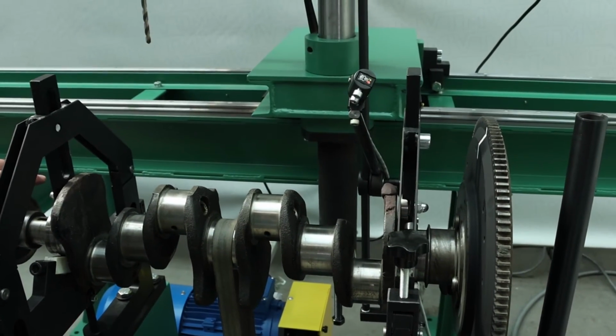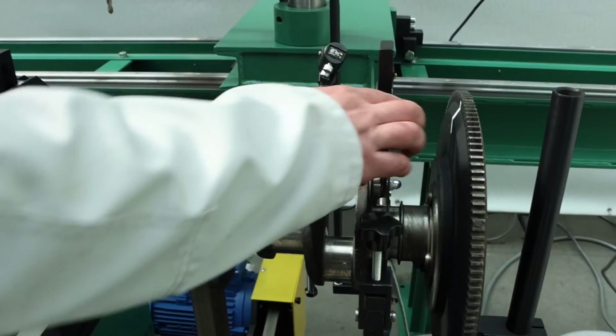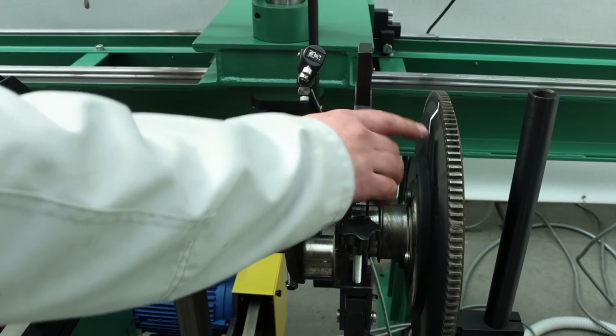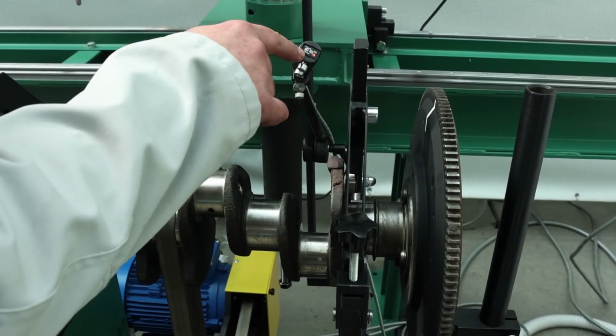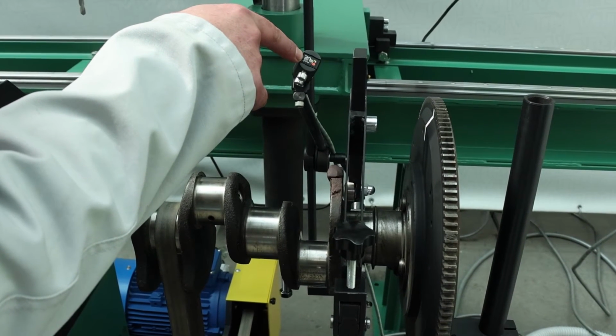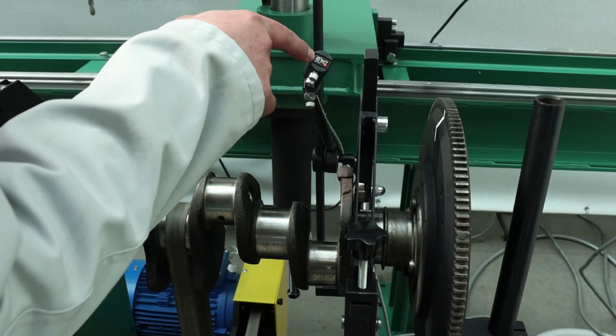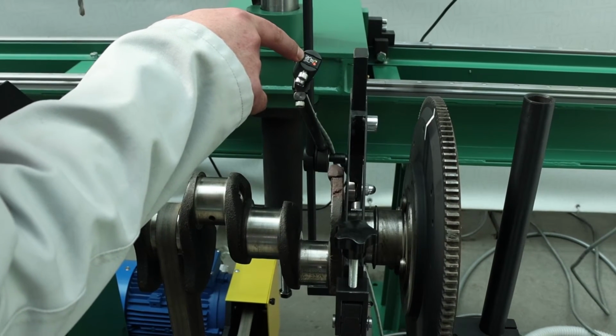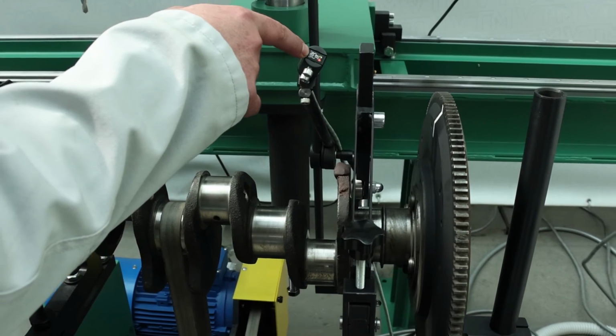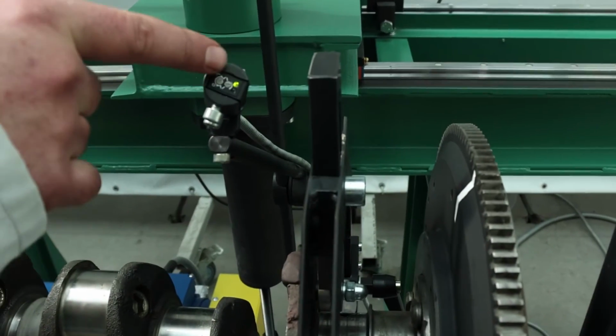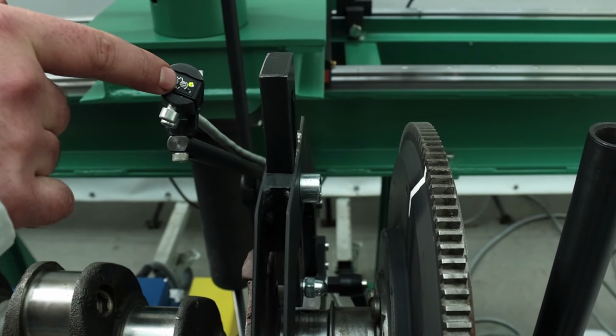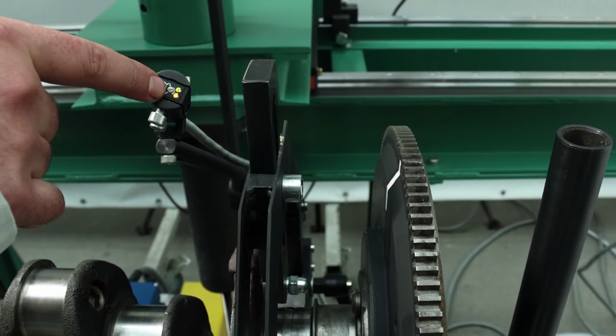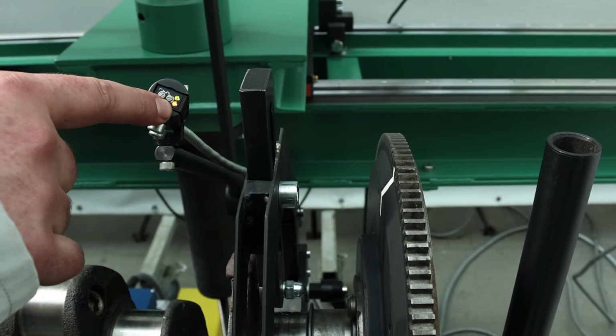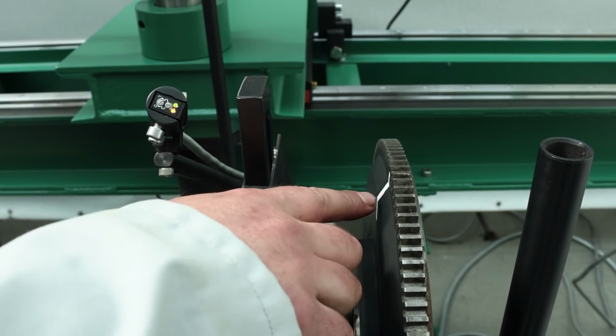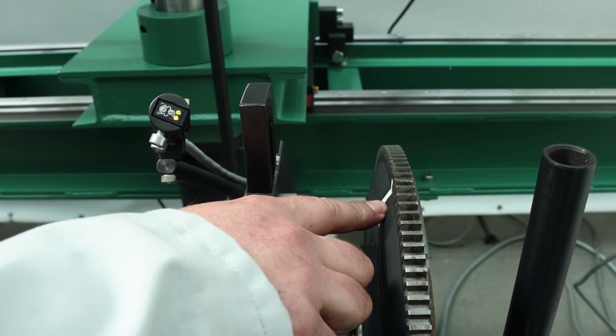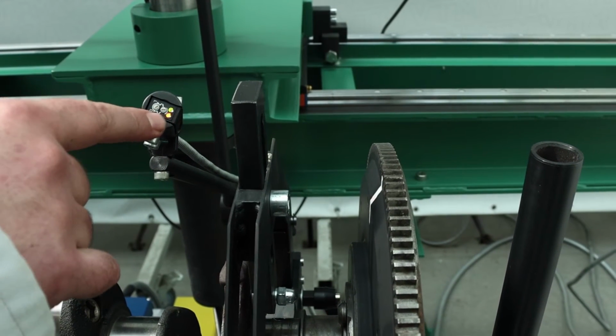To optimize the laser setting, a contrast mark should be made, preferably on a dark background. And set the switch, potentiometer, upper to position L. So that would mean that the light mark is now selected. And then turn the second potentiometer from minimum to maximum, until the orange indicator lights up, at which point the laser beam should shine on the mark. And rotate until the red indicator light comes on.